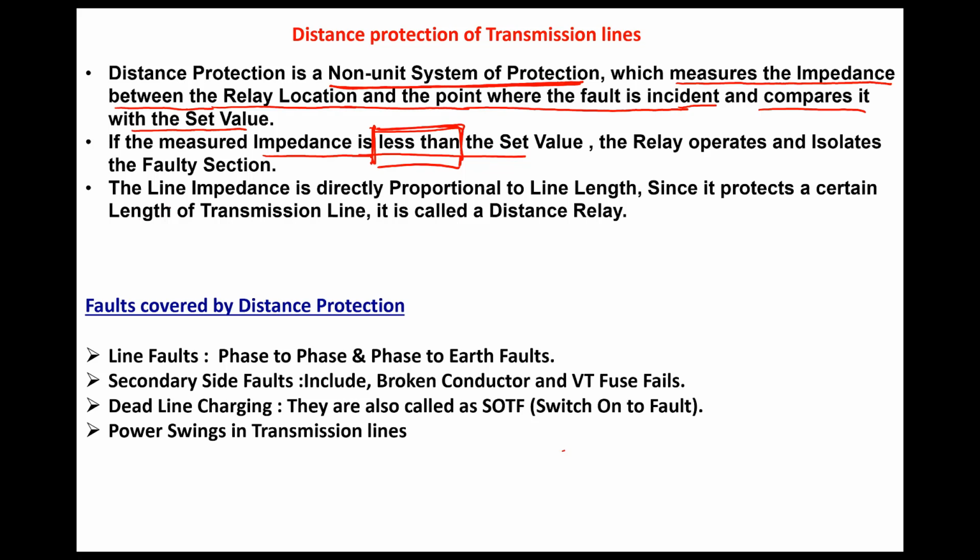Okay, the transmission line impedance is directly proportional to the transmission line length, because we are considering only series impedance. So the series impedance of the transmission line is directly proportional to its length. Since the distance relay protects a certain length of a transmission line, it is called a distance relay. So that is the concept.